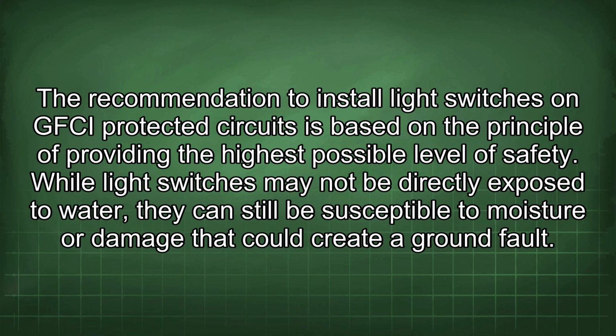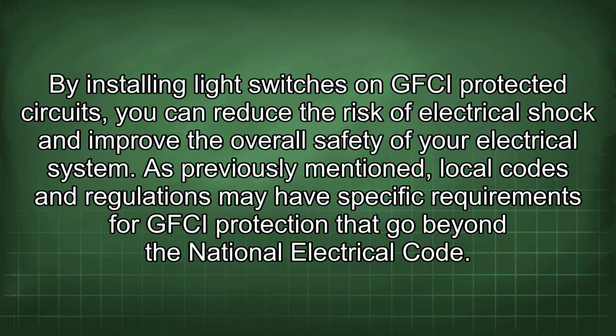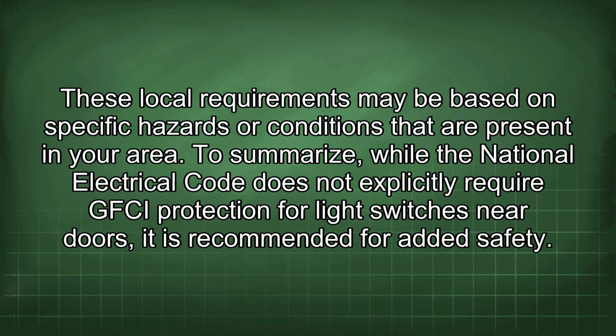The recommendation to install light switches on GFCI protected circuits is based on a principle of providing the highest possible level of safety. While light switches may not be directly exposed to water, they can still be susceptible to moisture or damage that could create a ground fault. By installing light switches on GFCI protected circuits, you can reduce the risk of electrical shock and improve the overall safety of your electrical system. As previously mentioned, local codes and regulations may have specific requirements for GFCI protection that go beyond the National Electrical Code. These local requirements may be based on specific hazards or conditions that are present in your area.